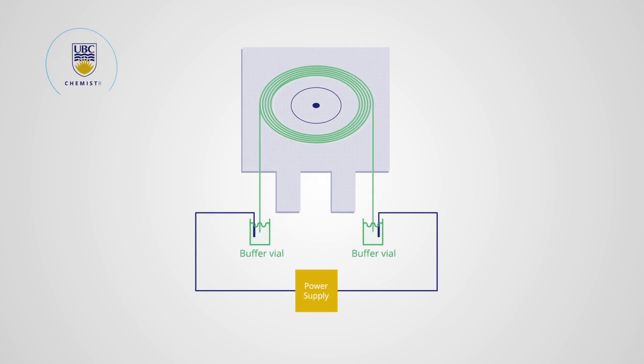the anode end of the capillary is dipped into the sample vial and a small plug of sample solution is forced in using pressure difference. The difference in pressure is established through the elevation of the anode end of the capillary, or through the pressurization of the sample vial using a pump.